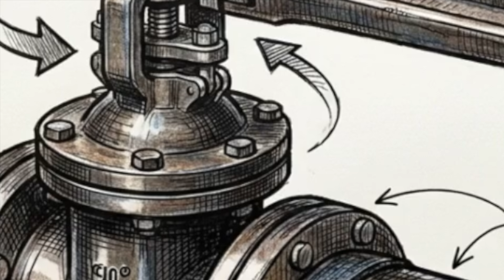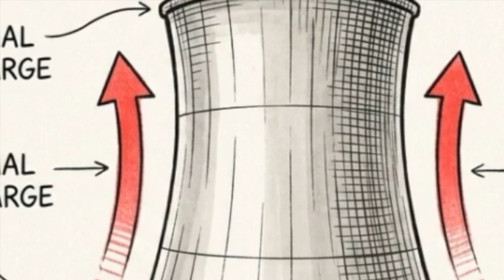We can apply this restorative logic to industrial infrastructure. When you look closely at modern manufacturing, you find a massive, expensive blind spot. Take a standard food processing plant. Their refrigeration chillers actively vent superheated 250-degree gas directly into the atmosphere through massive cooling towers. On the exact same property, that facility burns heavy volumes of natural gas in a separate boiler room. They do this simply to generate hot process water for washing and sanitizing.